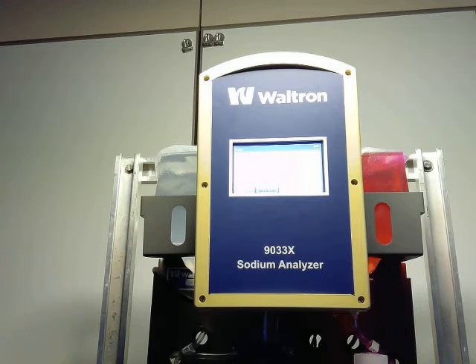The other thing with the calibration that's good to mention is that not only are we calibrating the analyzer for results, but we're also giving the probes a chance to see a high sodium standard. It wakes the probe back up. If we were to sit just reading DI water close to 0 for weeks and months at a time, that will certainly slow the response of the electrode. Then when it sees a higher sodium concentration, it will be very slow to respond. One reason we wouldn't want to go much farther than a month between calibrations is we just won't see the response from the electrode should the need arise. It wakes it up, makes sure we're reading accurately, and makes sure that everything else is working properly within the analyzer.